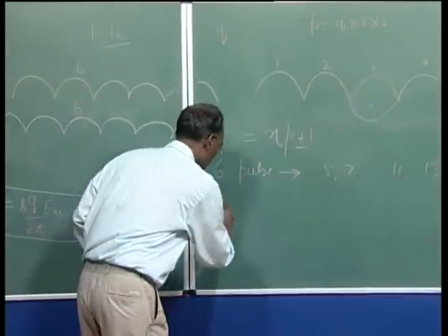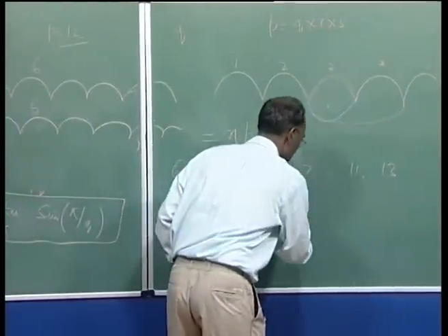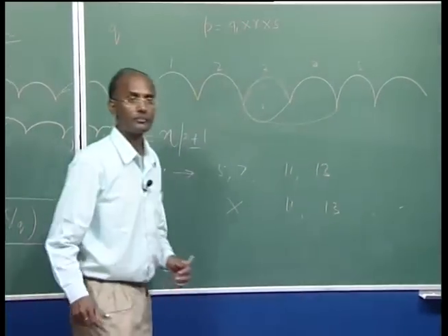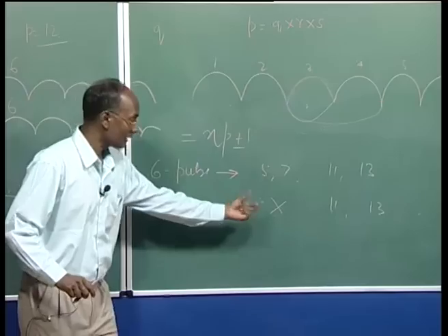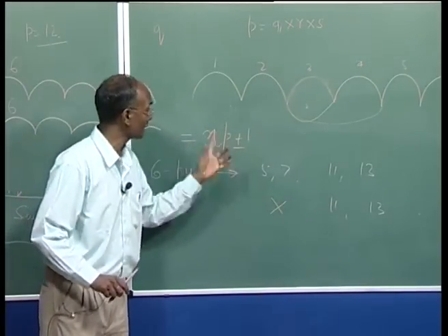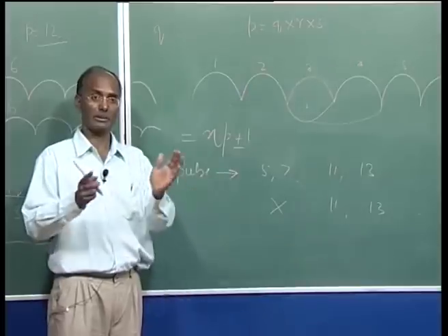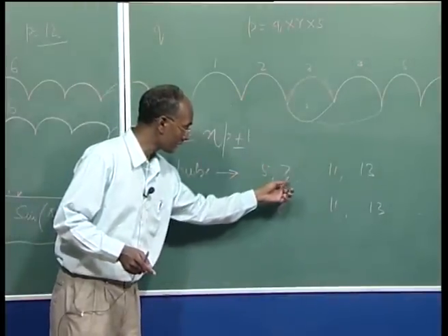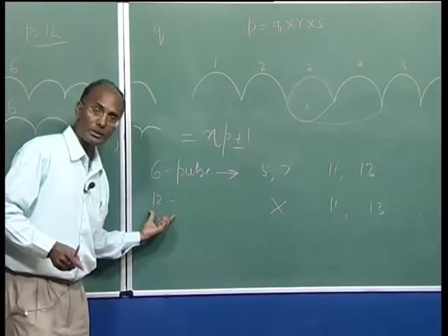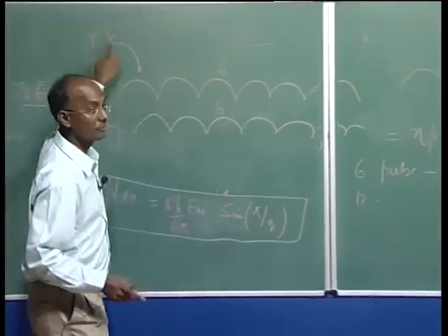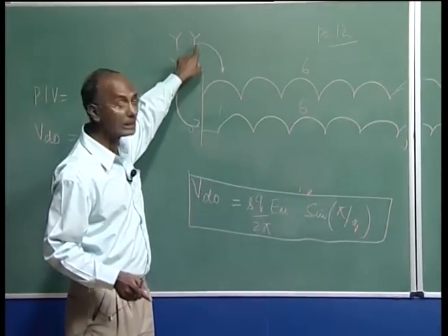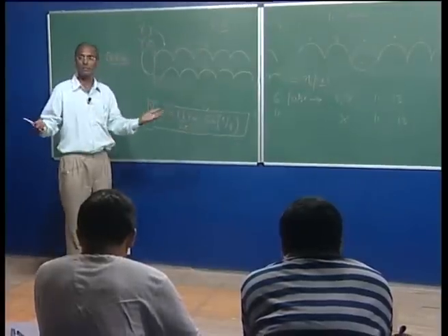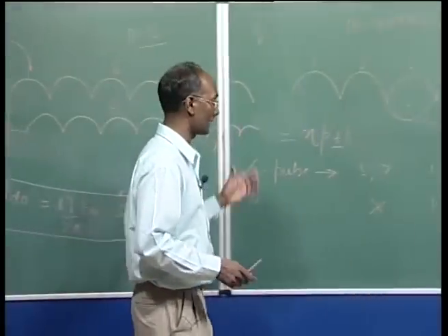Now, if you are going for 12 pulse, you will find these are cancelled. What happens is that they are cancelled by the star-delta transformer connection itself, so they do not go to the AC side due to that shift. The 5th and 7th will not appear in 12 pulse operation due to this phase shift. Whatever is generated is cancelled by the negative voltage, and when added together it goes to 0, so it does not enter the AC circuit.